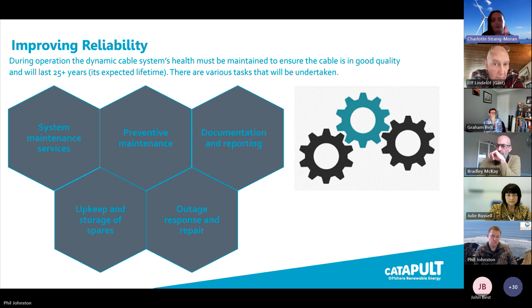You could use condition monitoring for that, or just heightened inspection. Documentation and reporting is key, keeping notes of different things that can occur to your cable, benchmarking within your organisation, and upkeep and storage of spares. This means understanding the frequency of failures, what components are likely to fail within your cable system, and having the spares ready. And of course, response and repair - optimizing your repair strategy, being prepared to repair your cable in good time.